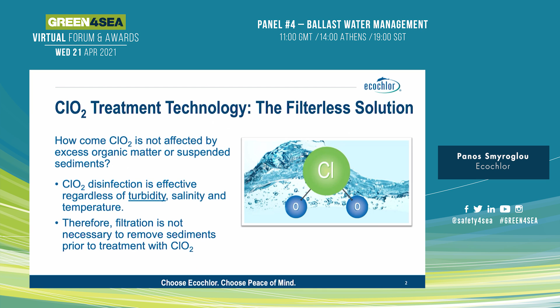Chlorine dioxide treatment technology has been used by us for many years, following land-based installations and for different applications. The fact of the matter is that chlorine dioxide disinfection is effective regardless of turbidity, salinity, and temperature. This is why filtration is, as a matter of fact, not necessary in order to remove sediments prior to treatment with chlorine dioxide.